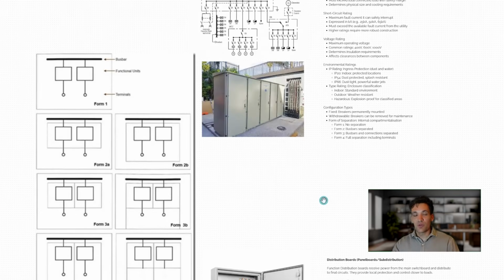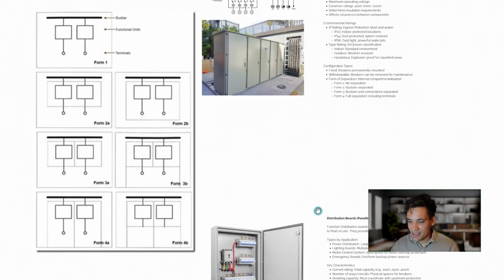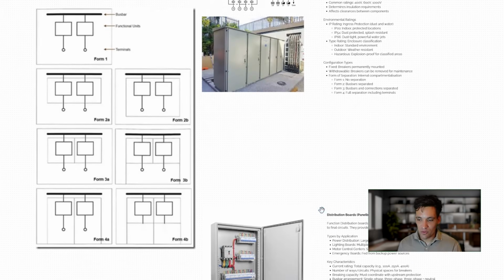So main switchboard is where the incoming power terminates. If we're then distributing power through the facility, we'll likely use distribution boards. Again, unless you have a massive house, your house isn't going to have sub-distribution boards. This will all be done in the single board where you have the incoming straight supply and maybe 8 to 10 outgoing circuits that feed your lights and direct to your appliances.